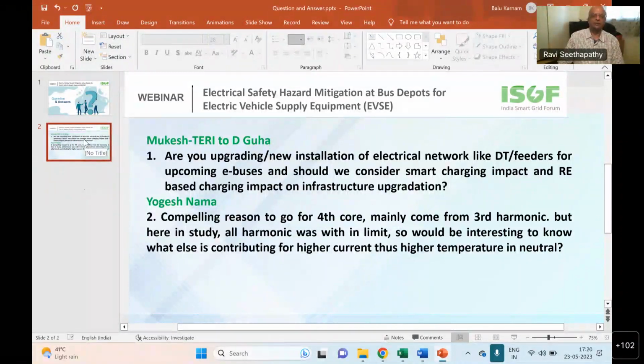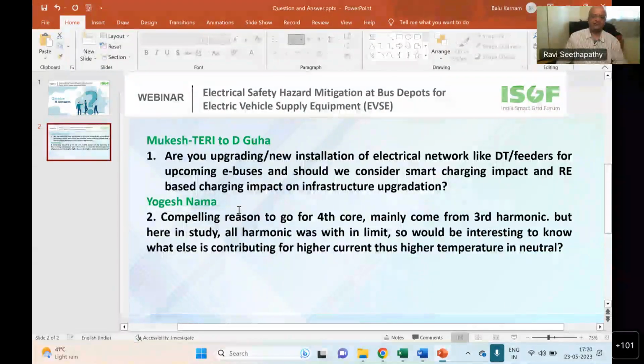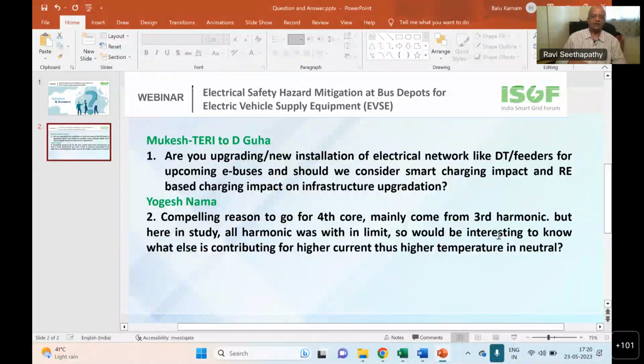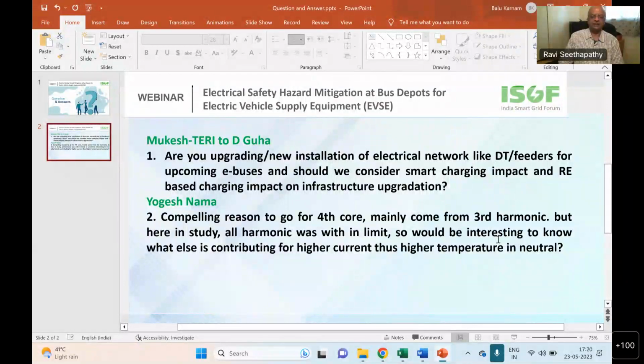So the question is, should we move to a four-core system? I see good comments—CESC says they've already got four core, and Ram Pillai, from his time at Tata, says they have four core too. So it looks like that leading practice has already been adopted by a few utilities. Perhaps others need to follow, or maybe standards haven't enforced it yet. Yesterday, in a conversation with another utility that Reggie was chairing, it didn't appear they had gone to four core—so different people are on different wavelengths here. But third harmonic isn't the only cause of heating in the neutral; other factors raise the current magnitude too, due to other things happening in the utility.